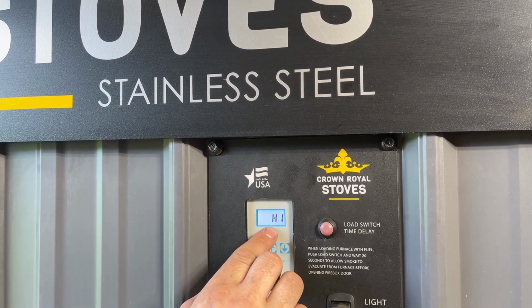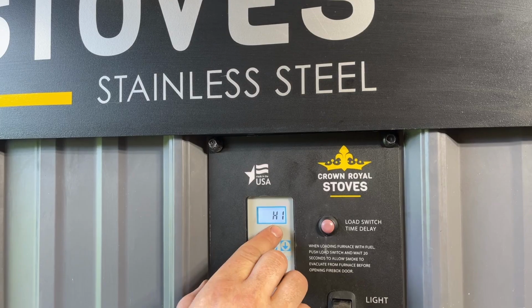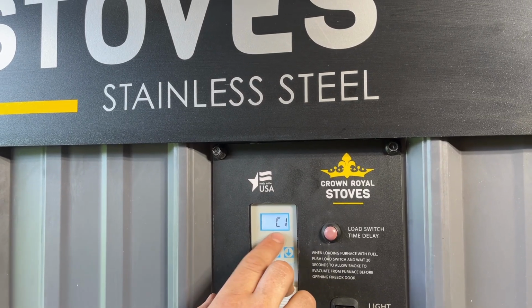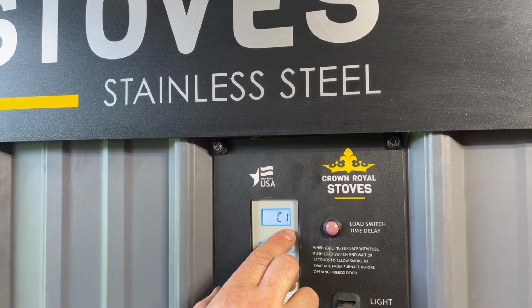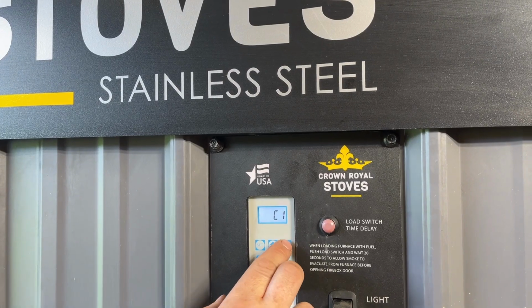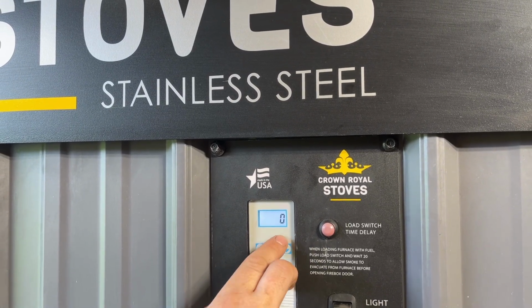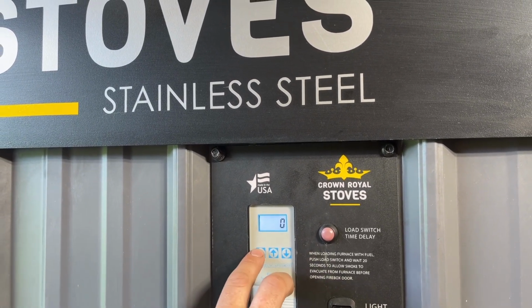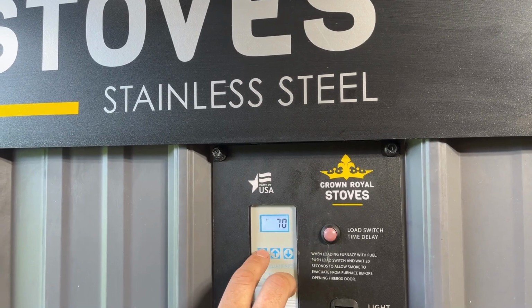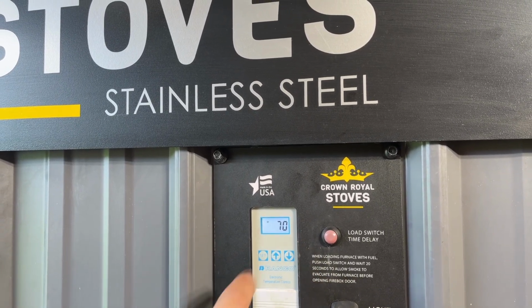This is really important to check: make sure this is set for H1. If it's set for C1, the Aquastat is set for cooling and your stove will not work properly. The next setting you don't have to worry about. Just make sure it says 0 and hit set again, and it'll take us right back to our current water temp.